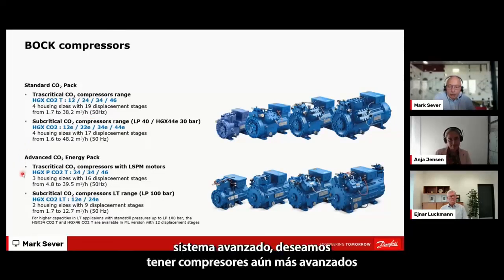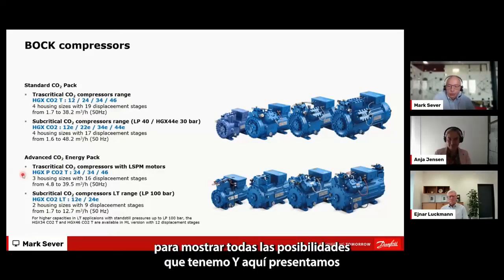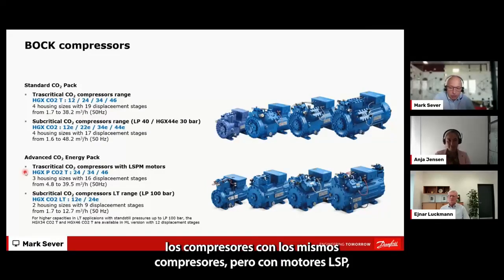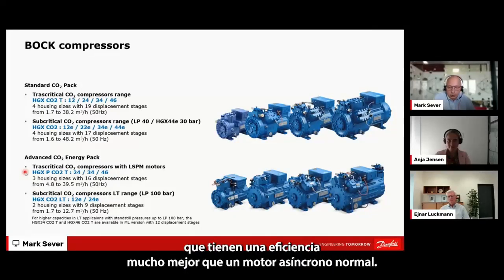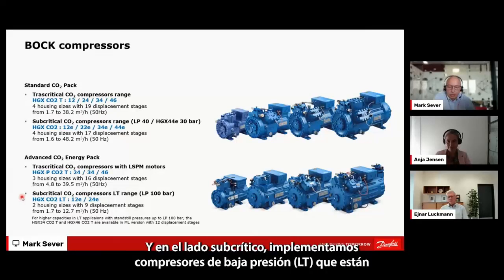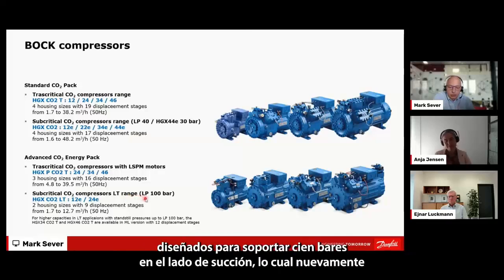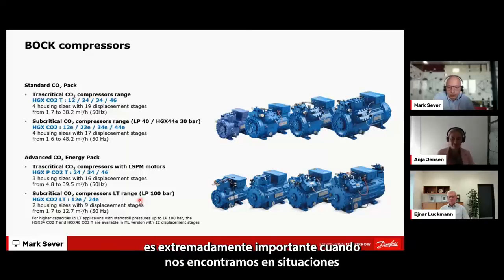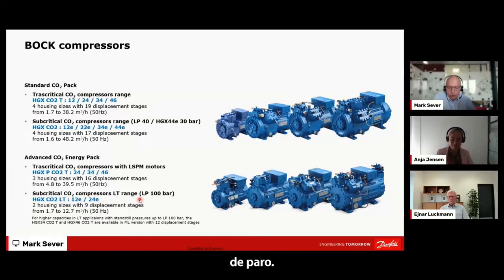On the advanced system, we wanted even more advanced compressors to show all possibilities. We introduced the same compressors but with LSPM motors, which have much better efficiency than the normal asynchronous motor. On the subcritical side, we implemented the LT range of compressors, designed to withstand 100 bars on the suction side, which is extremely important when getting into standstill situations.